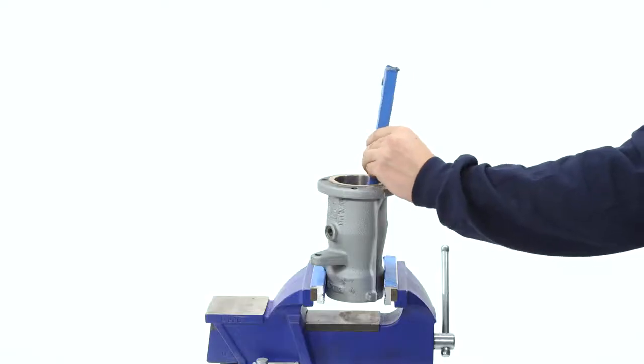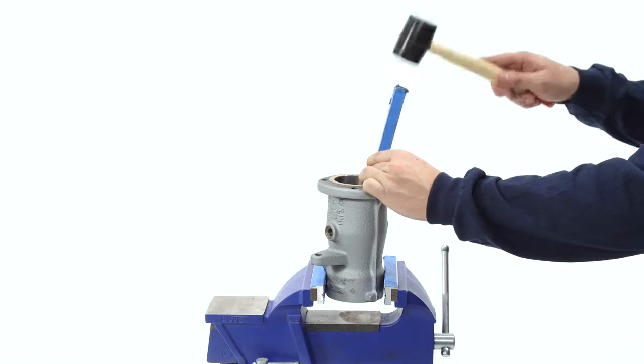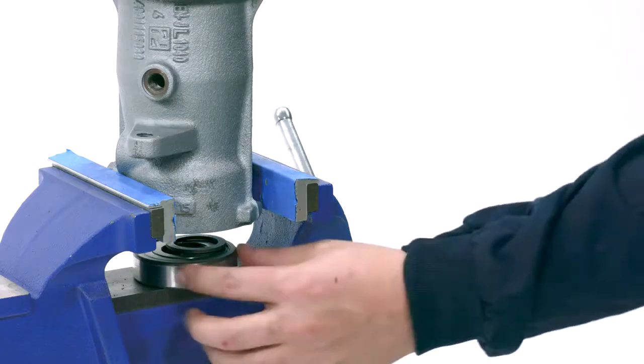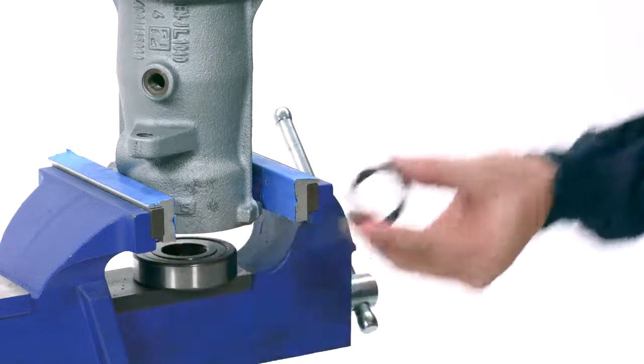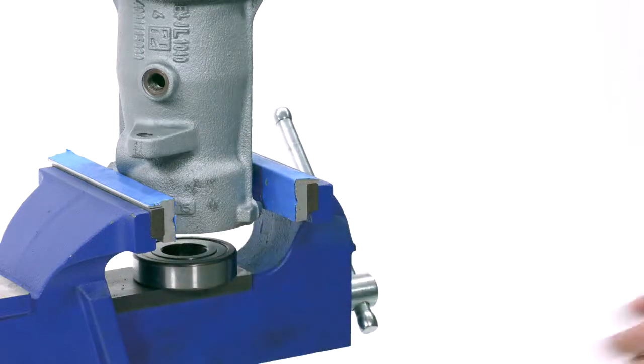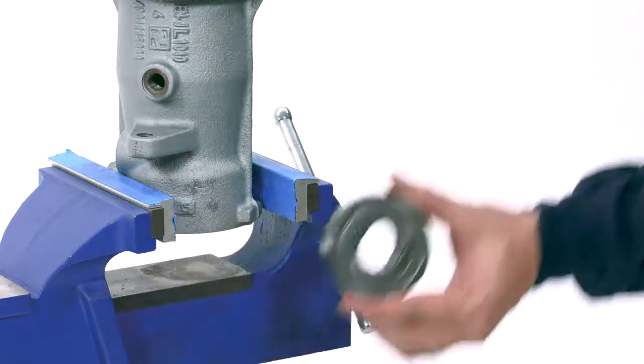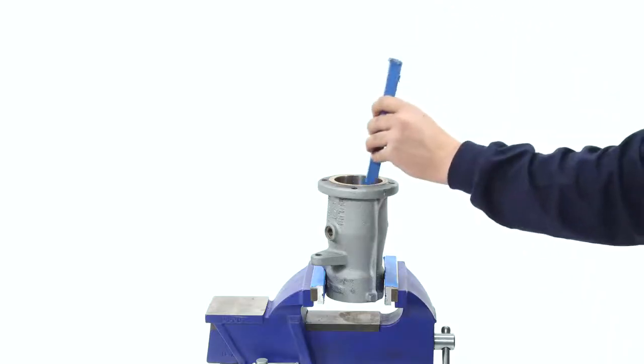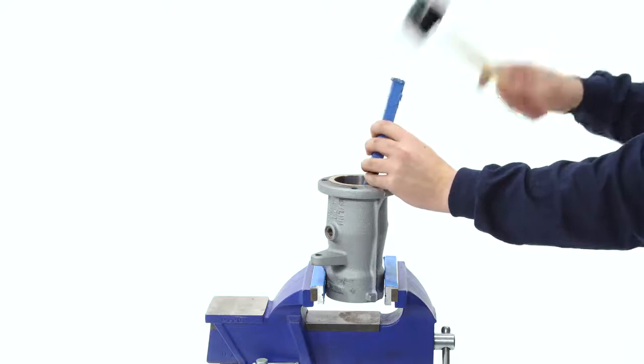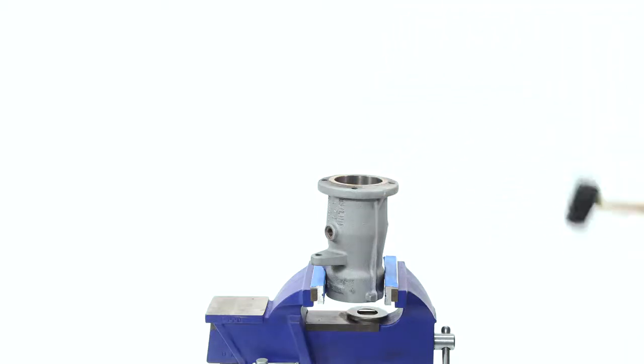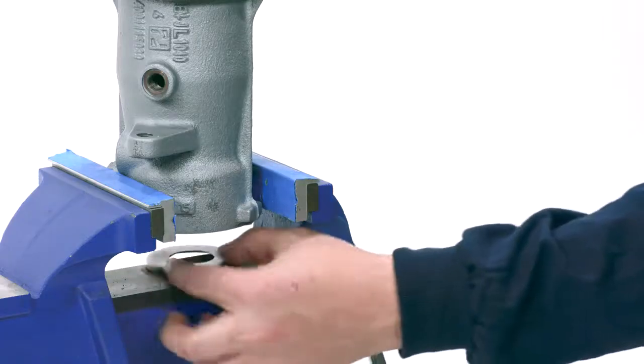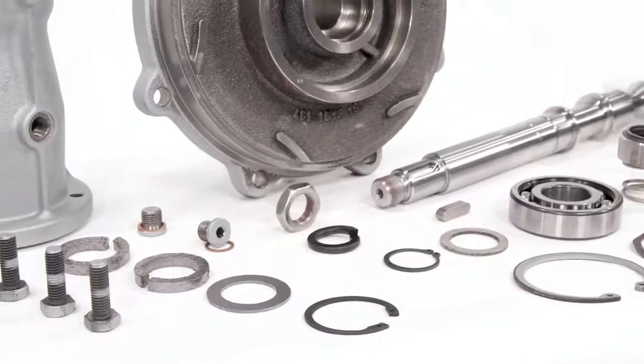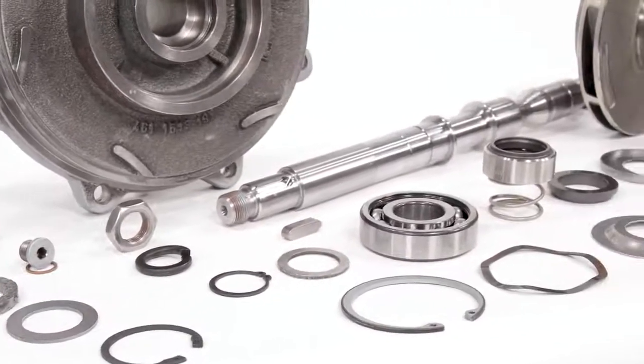With a dowel rod and hammer, carefully tap the bearing out of the bearing housing. Remove the bearing spacer that was behind the bearing in the housing. Gently use a rod and hammer to remove the grease cover. Your Allweiler NTT series pump is now fully disassembled.